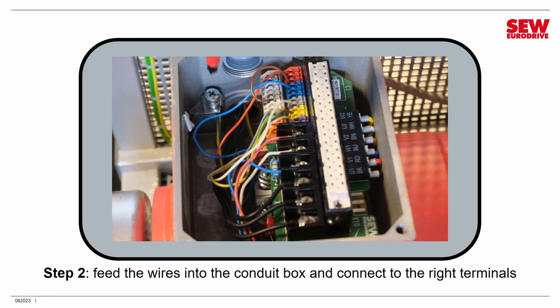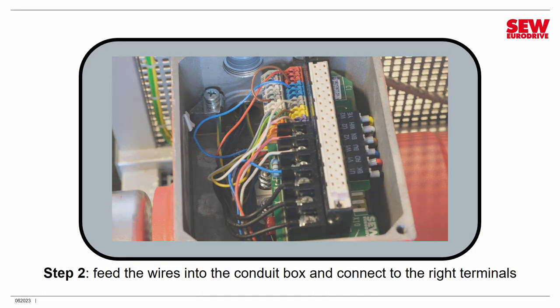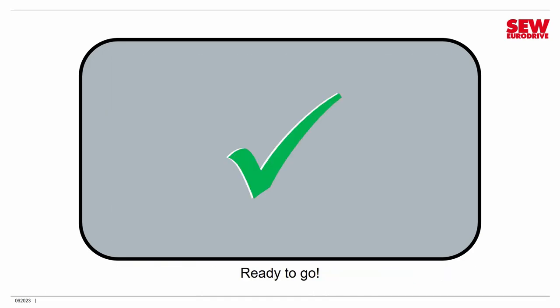The last thing to connect is the protective earth or ground connection. The wire is already in place, but I do have to tighten the screw down. Note that this connection is in the conduit box itself — not on the main circuit board, so it's in a different location. And that takes care of wiring up the MOVIMOT to power.